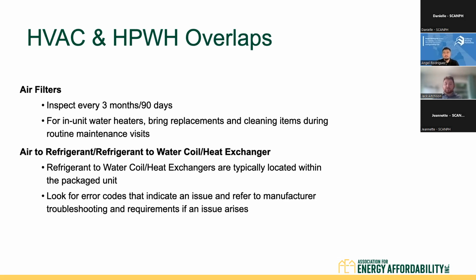Refrigerant to water coil / heat exchangers are typically located within the package unit. So that's going to be in your outdoor unit or in your residential heat pump water heater, in the tank and in the top. Ultimately, you should not be inspecting these or cleaning these. If you're replacing the air filter properly, you shouldn't have any issue. They are protected by the air filter. However, you should be looking for error codes that indicate an issue and refer to manufacturer troubleshooting and requirements if an issue arises. Ultimately, heat pump water heaters, especially commercial size heat pump water heaters, are expensive right now as the market is transforming to them being the norm. So you really want to make sure that you're not trying to clean these coils and cause issues with the unit. If you do see an error code or you do see an increase in electricity usage for whatever reason due to an issue associated with the unit, you should be contacting a vendor.